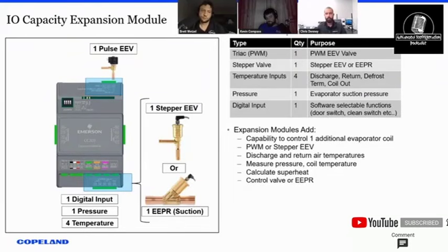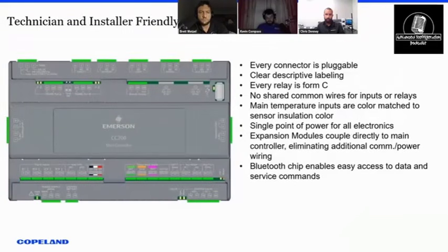the max right now. Another tidbit I was going to mention about the pressure transducer, if the manufacturer is using multiple coils and they're using an additional transducer, we have some redundancy built in there where if we lose one of the transducers, it'll fall back to the available one. So little added bonus for those that are using that feature. I'm sure you got some questions in the audience.